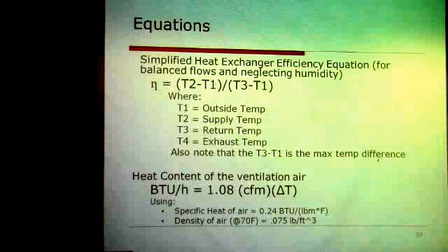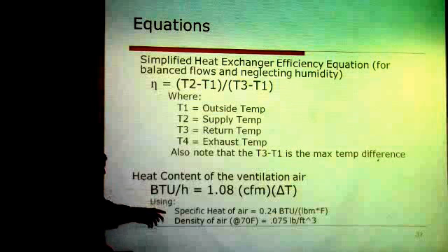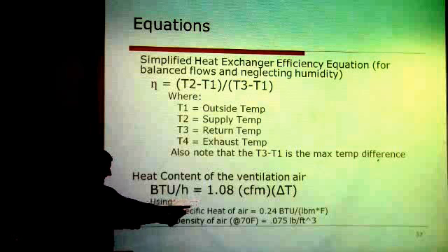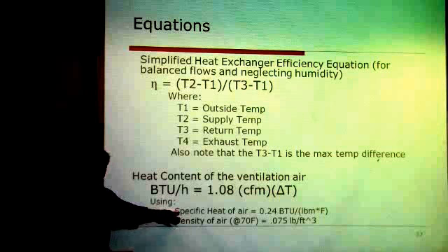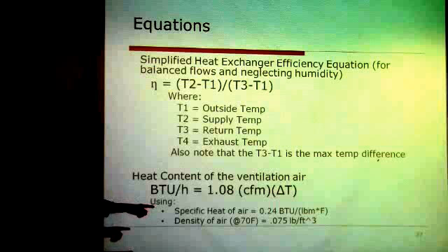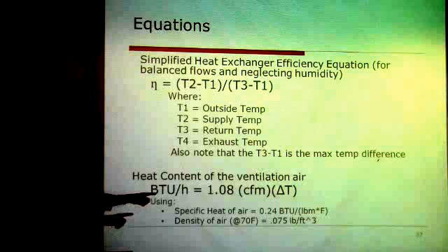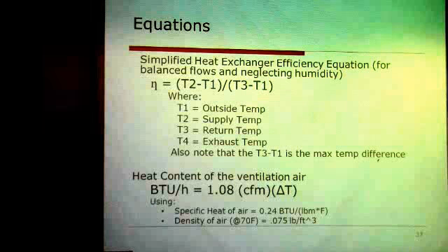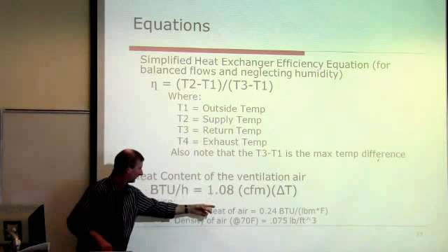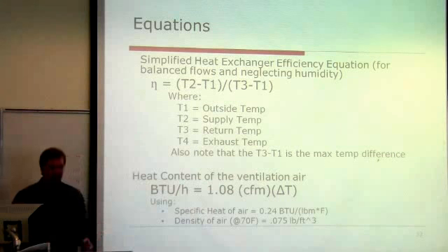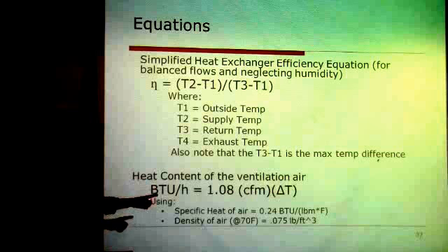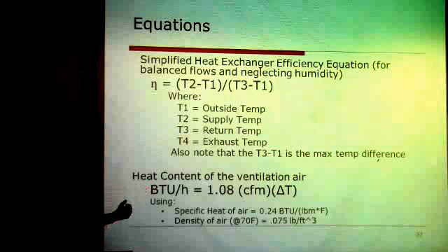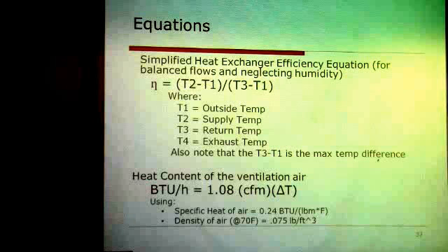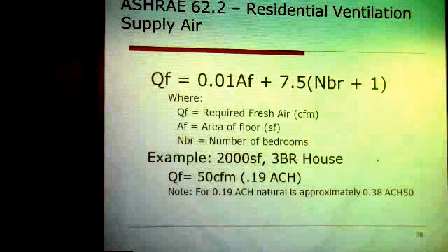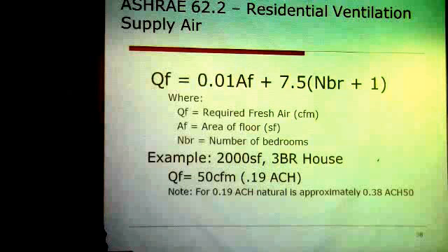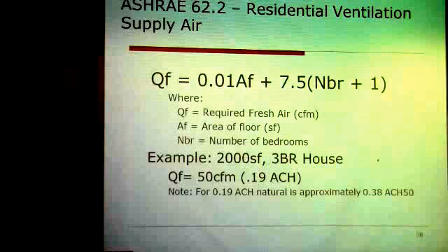And let's see. This 1.08 just comes from taking the specific heat of air, times your density, which gives you pounds, and then CFM, and then times 60 to convert from minutes to hours. So if you take 60 times 0.24 times 0.075, you should get that factor of 1.08. Any questions on that? I figured I had to put a few formulas in since this was an engineering class.